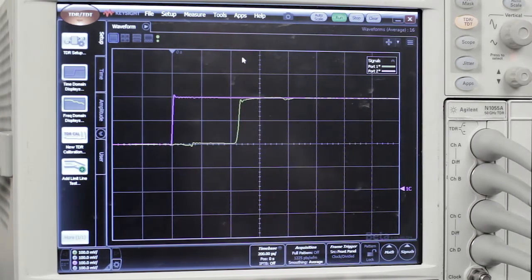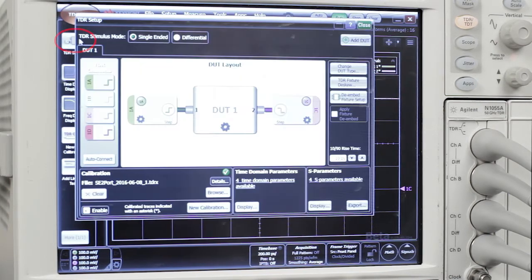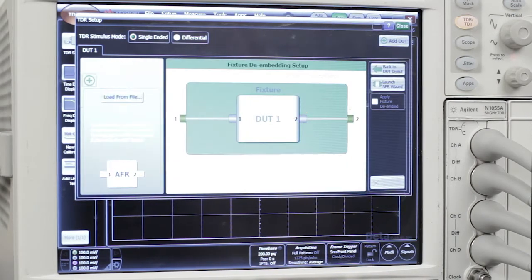Now that we've calibrated the TDR, we're going to use the calibrated TDR to characterize our fixture, and we can start back in the DUT setup. We call up the de-embedding menu, and that lets us launch the automatic fixture removal wizard here.